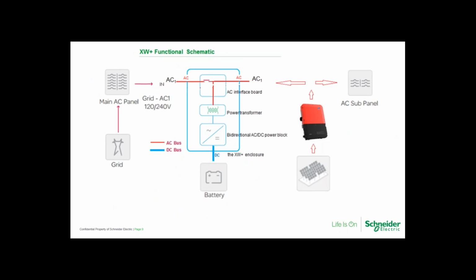So here we can see a functional schematic of an AC coupled system. AC coupling, again, means that the grid is merely passing through the XW. So anytime the grid is present, it's passing right on through. The term selling as it relates to the XW is defined by enabling grid support. And that's typically done when you're DC coupling, because you have an external source of power that's dumping power into the battery, and then the XW is drawing off that same battery to prioritize the load, and if there's anything left over, it'll push it back toward the grid.